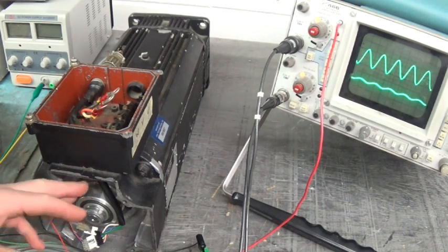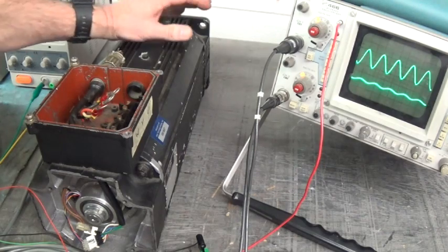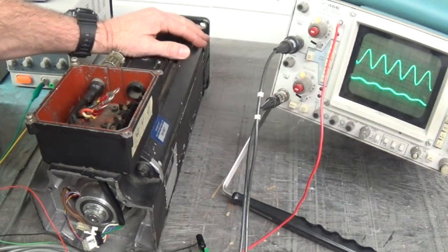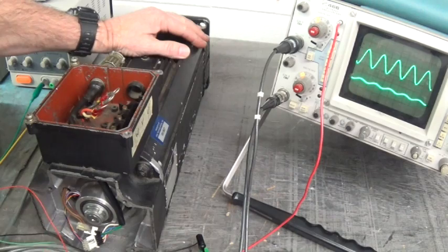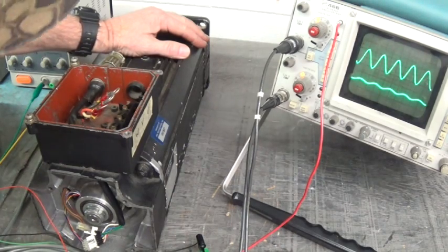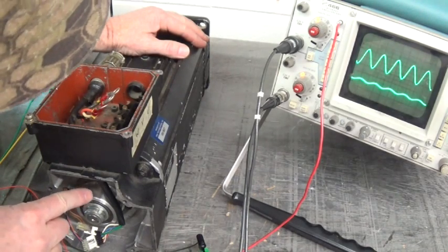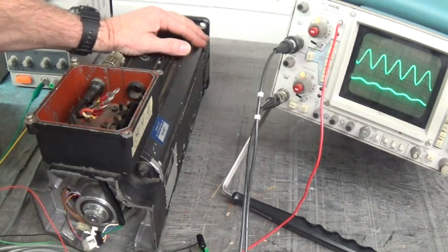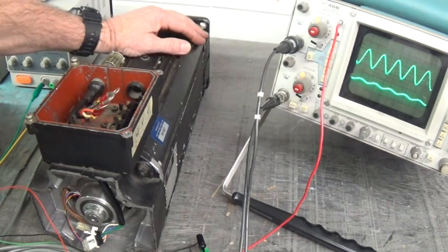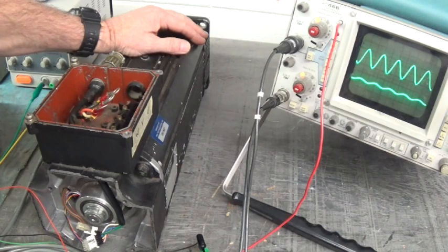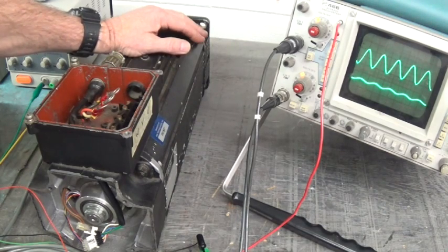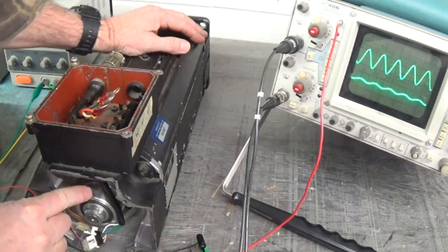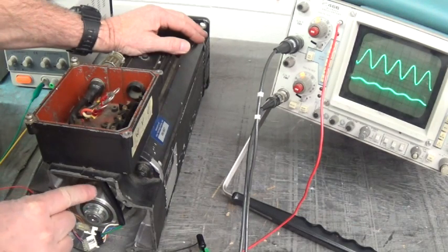This resolver is timed to the poles of the motor. This motor will not run right based upon that feedback if it's not timed to the poles of the motor, so we have to document the position of that resolver.